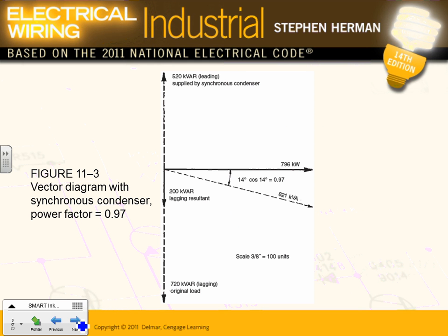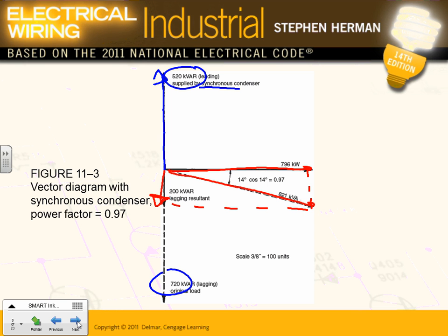Now, because that sucked, look what they did, guys. They added a capacitor bank. So I actually have a synchronous motor added. So look what happened. I added a synchronous motor equivalent to 520 kVAR, and when I added it to the 720, ultimately my triangle shrunk. My true power continued to be the same, then my apparent power also got smaller. Can you see that, instead of my true power being here, I got this leg going down? I don't know if you can see that.